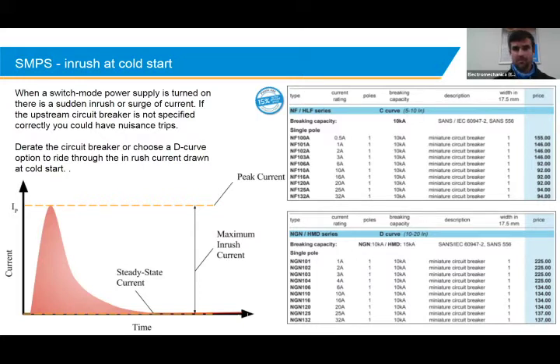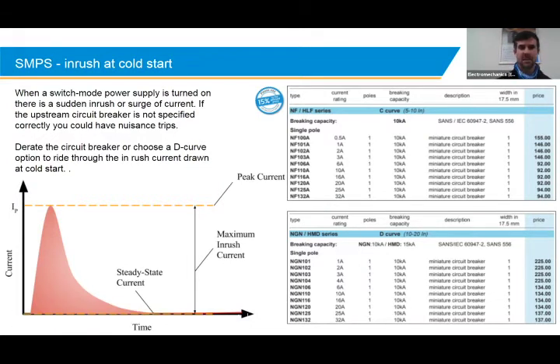There's two ways to get around this problem. Number one is increase your circuit breaker's nominal current. I typically go for the 6 amp, like NF106 for your single phase input breaker. It gives you 6 amps at 5 to 10 times inrush current. It's enough to cover a wide range of power supplies that use single phase. Also, the reason for the 6 amp is you note that it's a little bit cheaper than anything lower than that, the 3, the 2, and the 1 amp, namely. So the 6 amp is one choice you can go for. If your typical power supply nominal current is, say, half an amp or 1 amp, then multiplying that input by about 5 times should be enough to save you from a nuisance trip. Another way around the problem would be to use a D-curve breaker, used primarily in motor starting direct online applications. But the D-curve has obviously the curve to filter out this type of inrush current that you could experience.